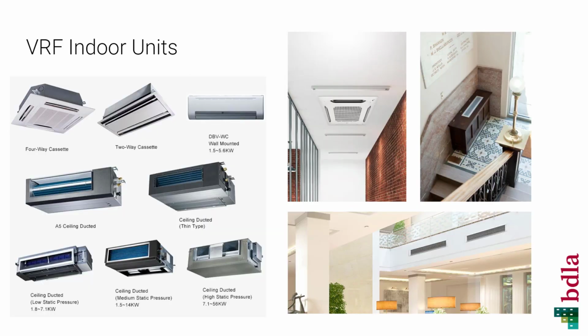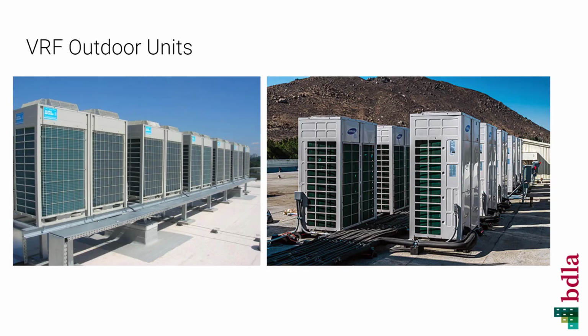This is just a look at some different options. VRF units are really customizable. You can pick from a whole different array of indoor units. These are just a few examples that can be integrated into an existing building or a new building. They're pretty easy to tuck away, like that example you see with the staircase where it's hidden entirely in a box, so it integrates well in a historic building. The outdoor units are much larger, but typically not as large as an air source heat pump, and they can be located on the roof of the building or outdoors adjacent to the building.